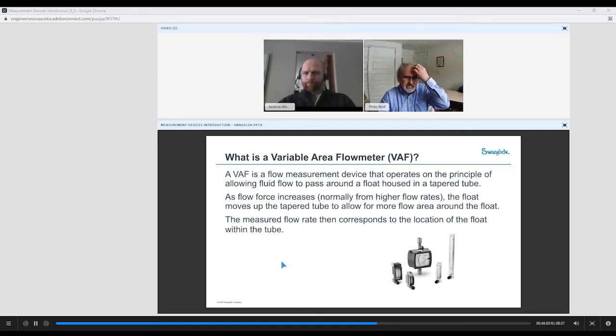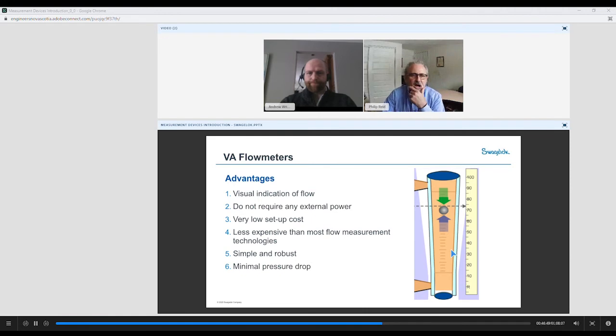Well, a flow meter is a device that operates on the principle of allowing fluid to pass around a float that's in a housing, and we'll take a little closer look at this later. And the tube is tapered inside here, and we'll see a slide in just a couple of minutes that shows this. As the flow force increases, normally from higher flow rates, the float will move up the tube, and the tapered tube allows more flow around that annular gap around the outside. So as that ball moves up in the tube, the tube becomes larger, and you get a direct indication at the front. The measured flow rate then corresponds to a location right on the tube. So let's take a little look at what we're really talking about here.